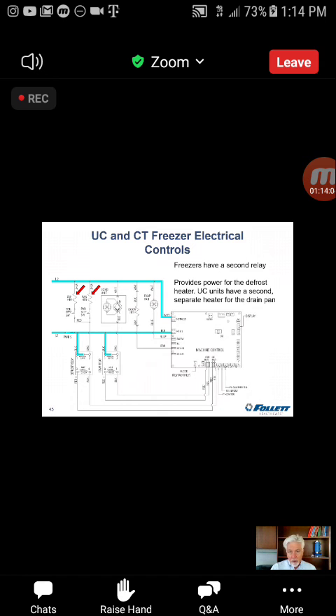That's just to prevent the water from refreezing. On the countertop units, it's all tied together, both the pan and the defrost heater itself. There is the P2 probe that I remember I was mentioning earlier. That's the one that measures the temperature of the evaporator coil, and we terminate that defrost when that probe gets to 5 degrees C, which is the equivalent of 41 degrees Fahrenheit.